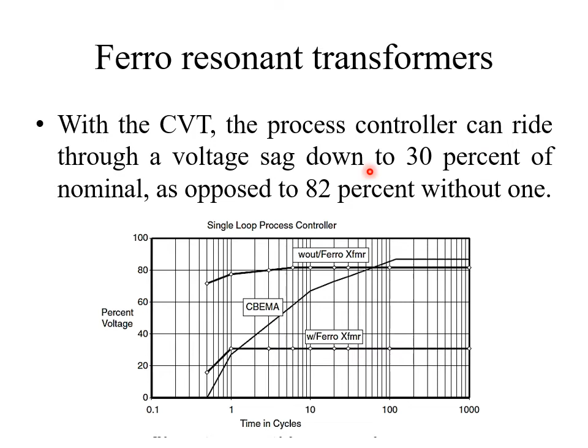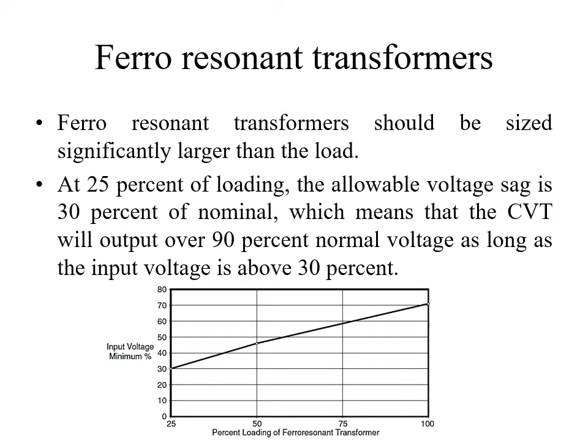In such a type, the loading also plays an important role. You see here the percent loading of the ferro-resonant transformer. If the loading is 25 percentage, then it is not a problem; 30 percentage voltage can be operated. But if the loading increases, then correspondingly the voltage level should also be increased. At 25% of loading, the allowable voltage sag is 30%. At 50 percentage of loading, the allowable voltage sag is approximately 45 percentage. At 75 percentage of loading, the allowable voltage sag is 60 percentage. And at 100 percentage loading, the allowable voltage sag is 70 percentage.